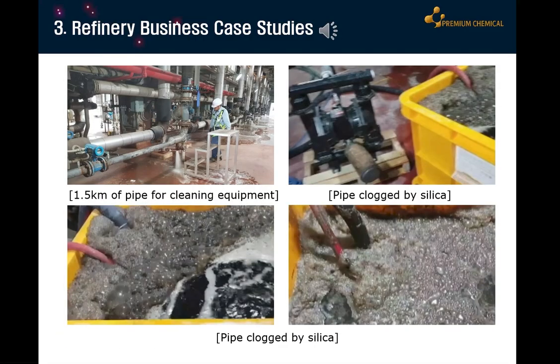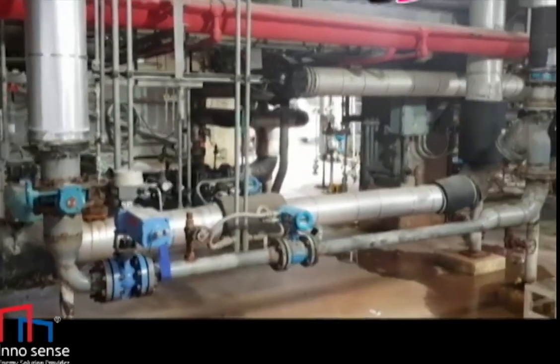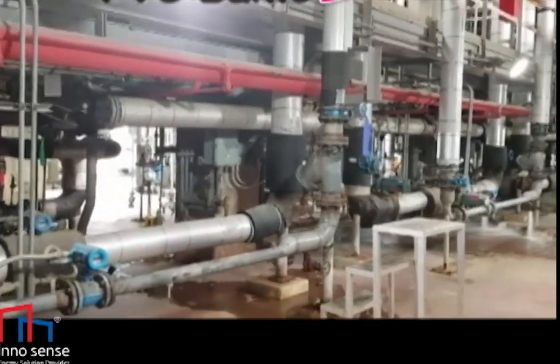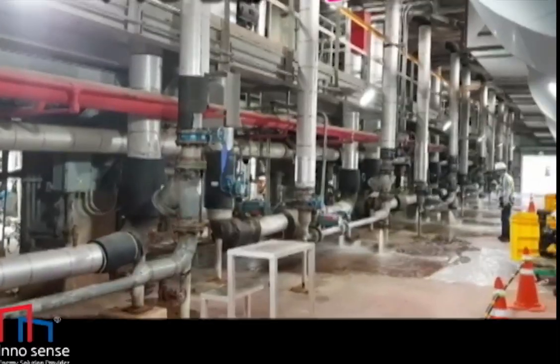The chemical cleaning process shown in this video removes scale from a 1.5 km pipe. The primary scale components are silica and limestone, with silica accounting for approximately 85%. Contamination levels within the circulating tank can be monitored in real time. In other words, the scale within the pipe is dissolved and released into the circulating tank.